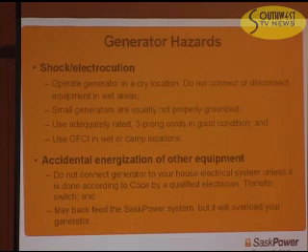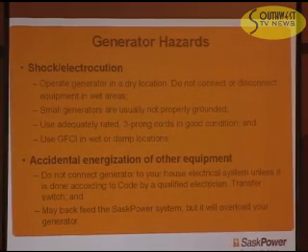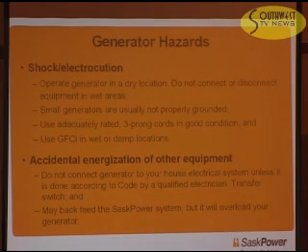Regarding accidental energization: some people are tempted to take their generator output and backfeed it into their house system as a quick way to get the computer or television going. Unless you have a properly installed system done to code, this is not a good idea. It may backfeed the SaskPower system, which is dangerous if workers are using proper work methods. It's also going to burn out your generator.